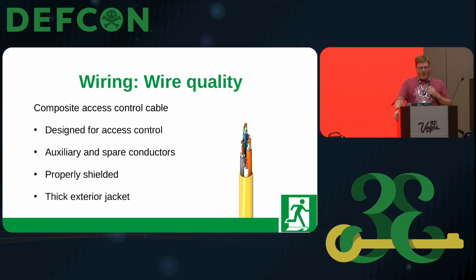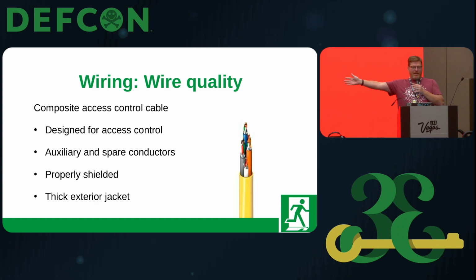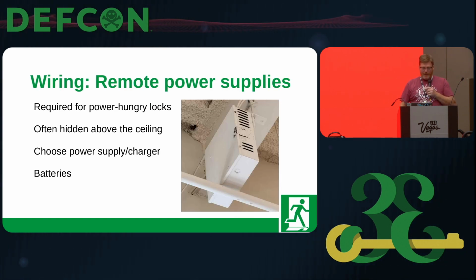So the answer to that is called composite access control cable. It's made by companies that design this for access control applications. It has all the wires that you need. They're all shielded where they need to be shielded. You can get them with auxiliary and spare conductors if you want to run a push button or other stuff. They're properly shielded, as I mentioned, and then there's like a thick exterior jacket. But the important thing is, if somebody has run this access control cable, you can look at it immediately and go, okay, this is suitable cable. I don't have to go figure out, did they run too thin a cable for this particular wiring run.